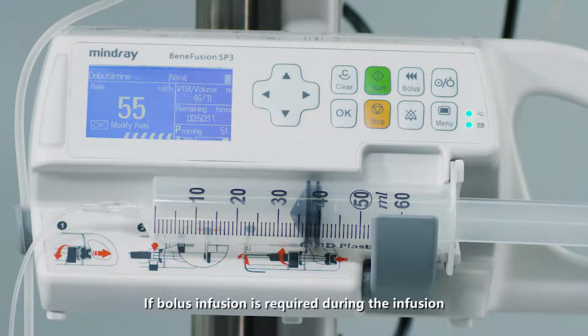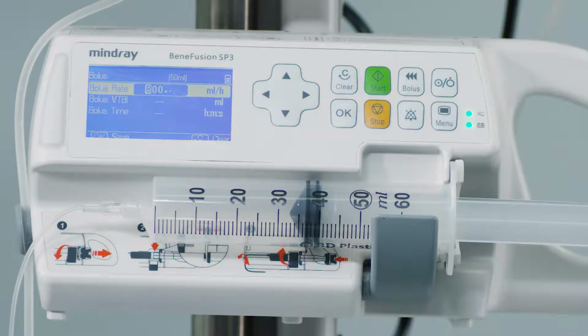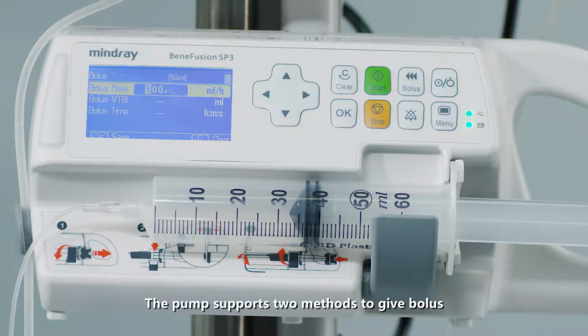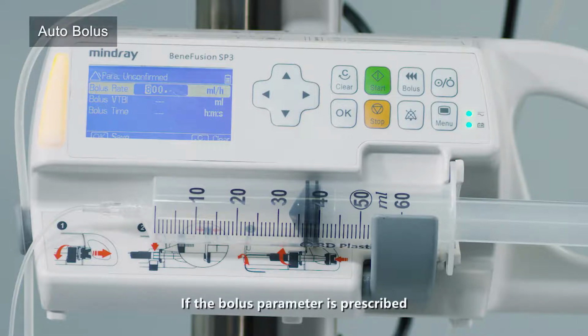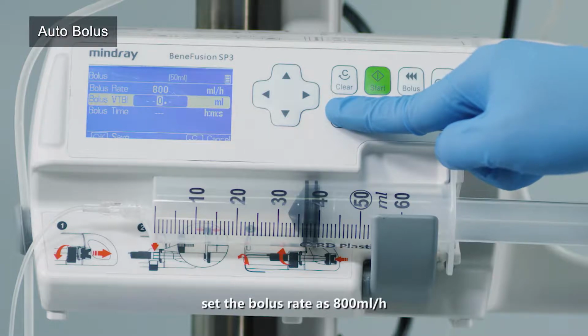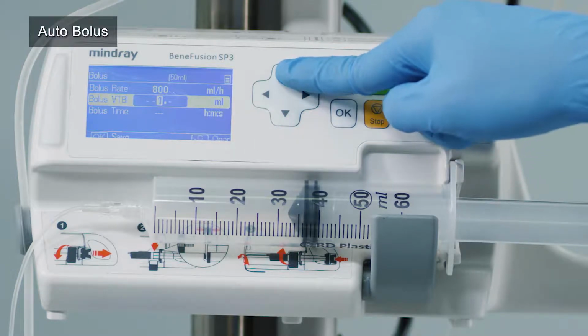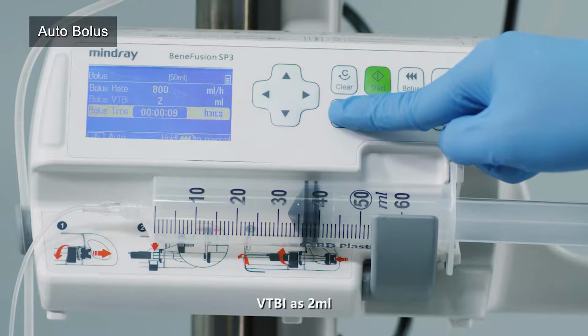If bolus infusion is required during the infusion, press the bolus key to enter the bolus setting interface. The pump supports two methods to give bolus: auto bolus and manual bolus. If the bolus parameter is prescribed, then auto bolus is recommended.